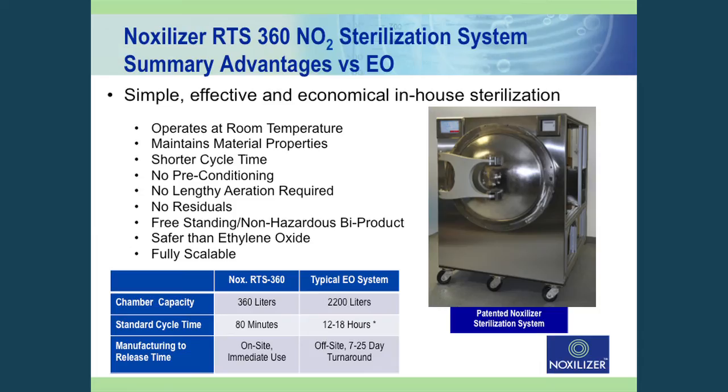The sterilizer we've been using for our testing is the RTS 360. It has 360 liters of usable space and is a room temperature sterilizer. The cycle runs off a microprocessor, pre-programmed with cycles validated for specific products. Cycle times are about 80 minutes. This is designed for on-site use — bring it in, plug it into the wall, and use it on-site.